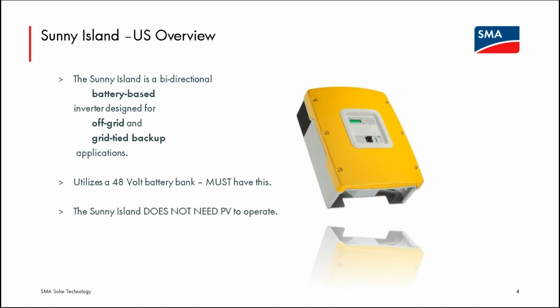But they know I only need that Sunny Island system to ride through for X number of hours. They're making sure that a very expensive saltwater fish tank has the ability to run pumps and keep a heat light on, keep a freezer from thawing. They have some desire to keep a load running for a short number of hours. But any long-term grid outage, PV or a generator likely would be required. But again, the Sunny Island only needs that battery bank to operate.